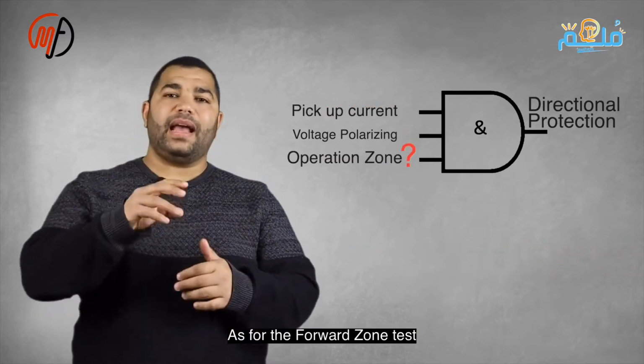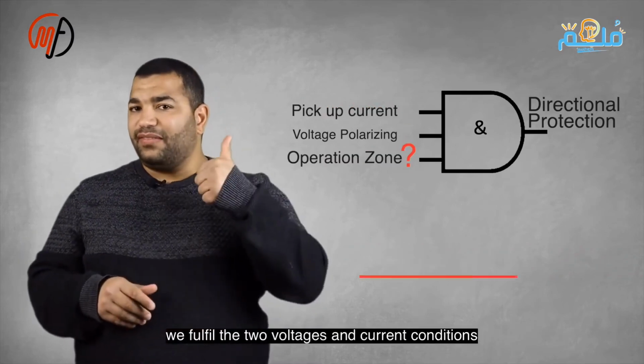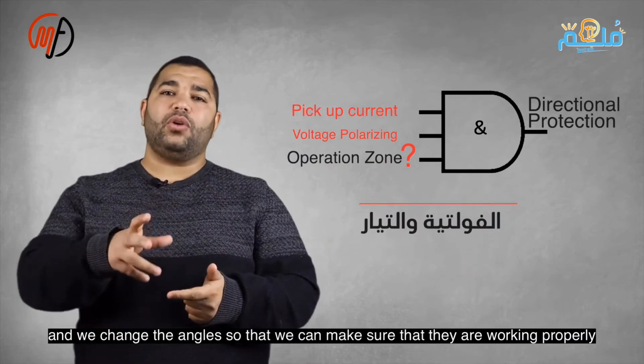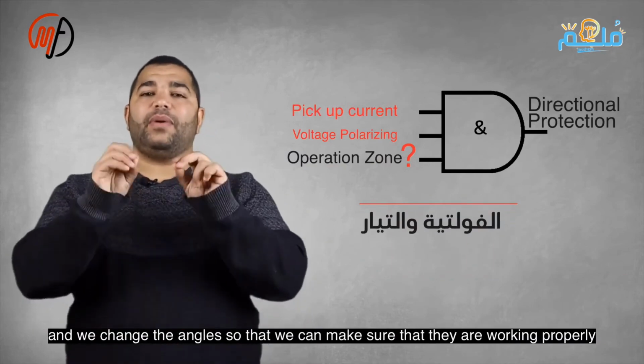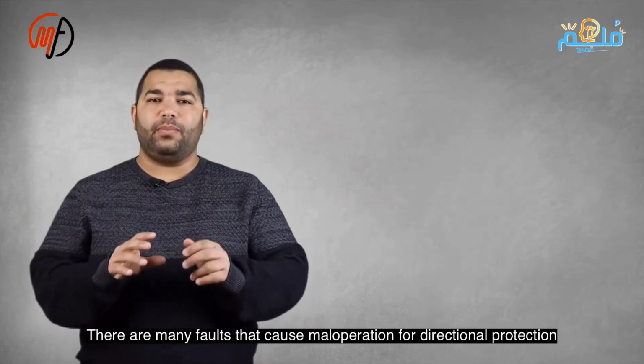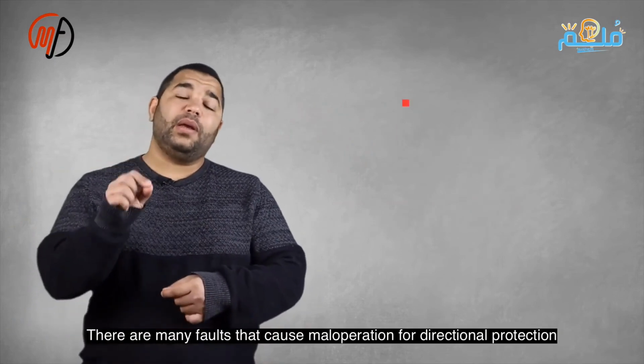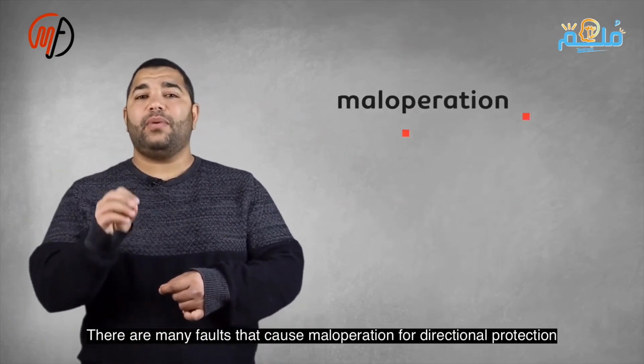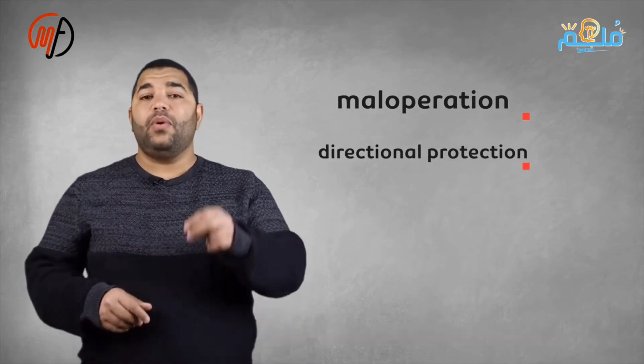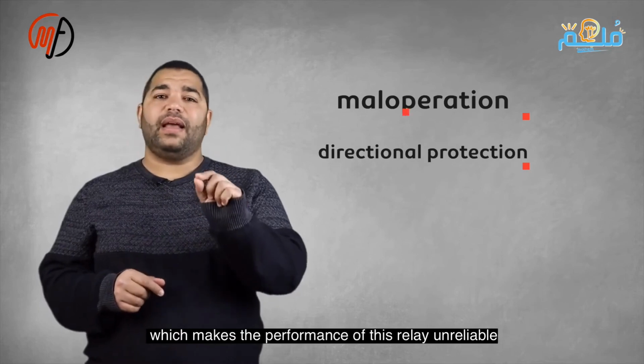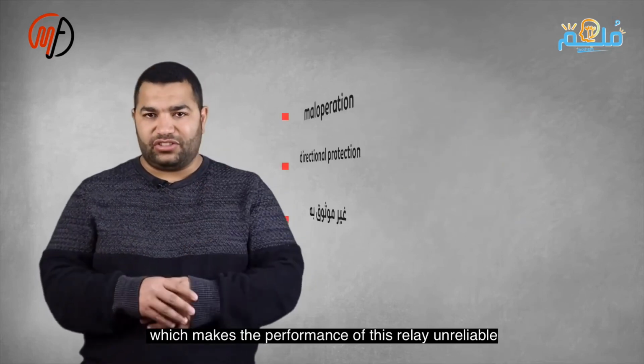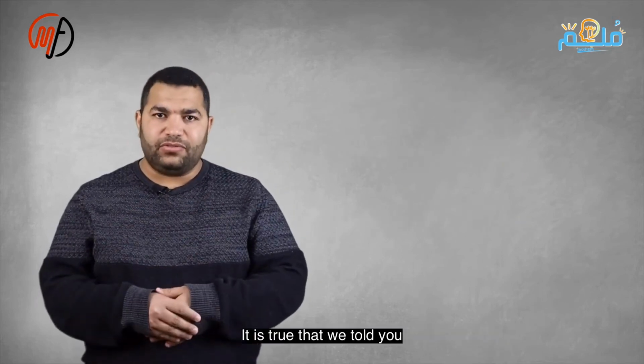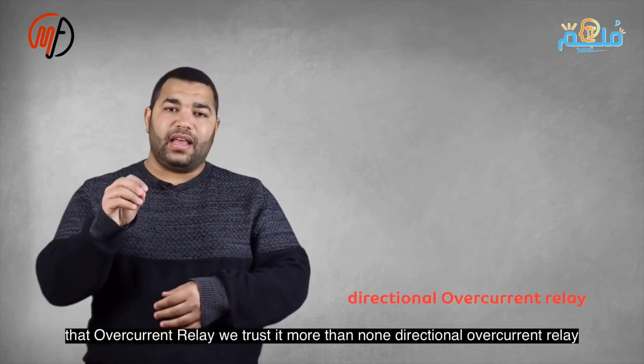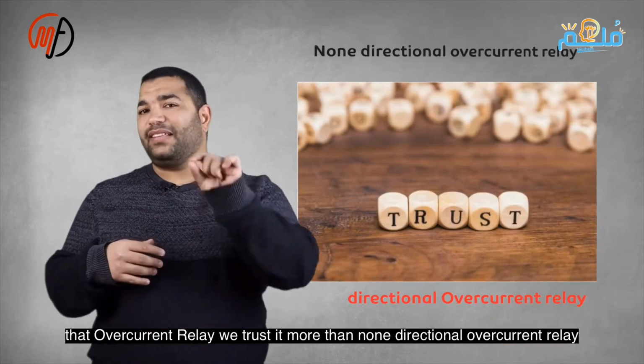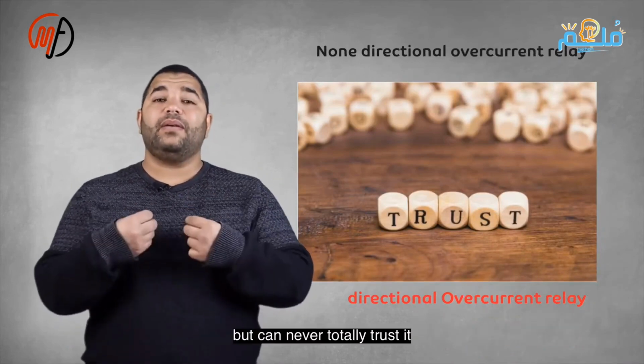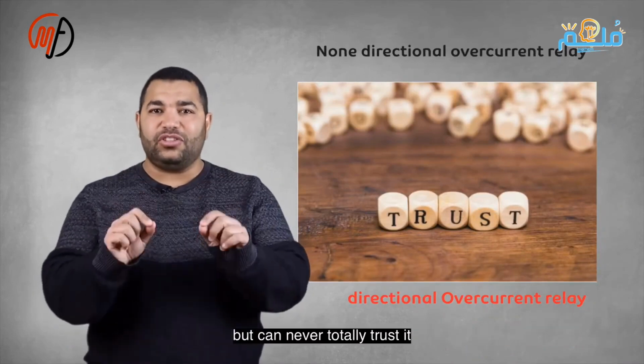As for testing the angles, we meet 2 conditions and adjust until we are sure of their values, ensuring that they are functioning correctly. Faults can cause operational issues or incorrect functioning of the directional protection. A 3-phase fault increases current and decreases voltage, complicating the use of voltage as a reference signal for fault current direction. Is it forward or reverse? A phase-to-phase fault changes voltage angles, affecting zones and potentially misidentifying fault directions. High impedance faults may produce currents below the directional protection setting.